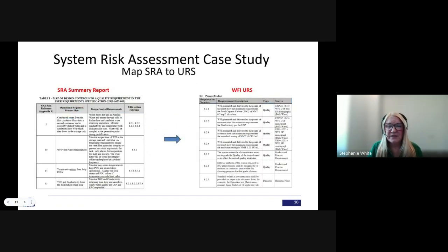When you get to the end of these, I usually do a summary report. In that summary report, I take all of the elements and map them back to the URS requirement. You can see I have these elements listed, the system risk assessment reference, which is why we have those numbers in them. Then we put down what the operational sequence was. I just take these columns out of the matrix and place them in this table for the summary report.